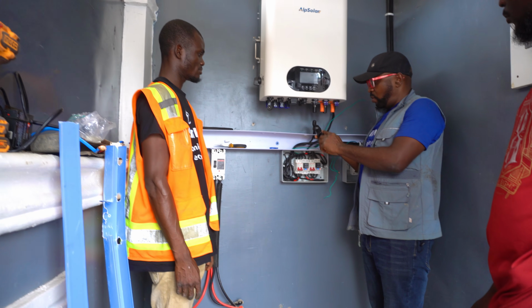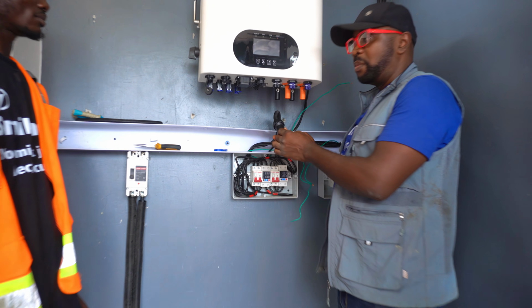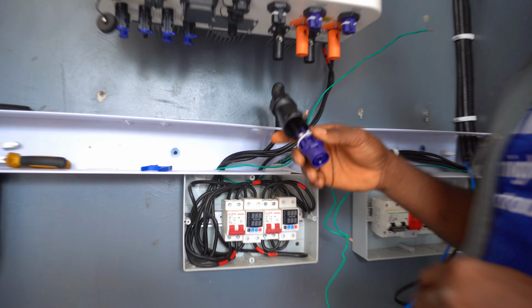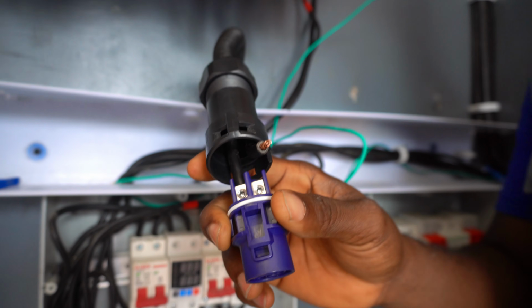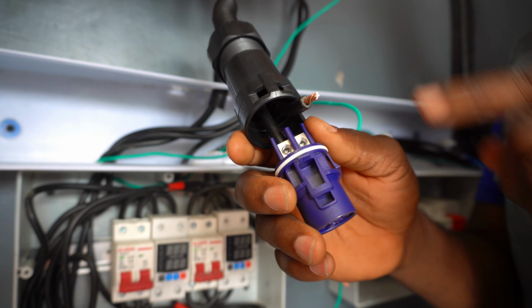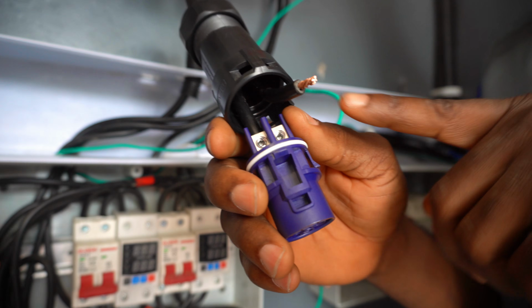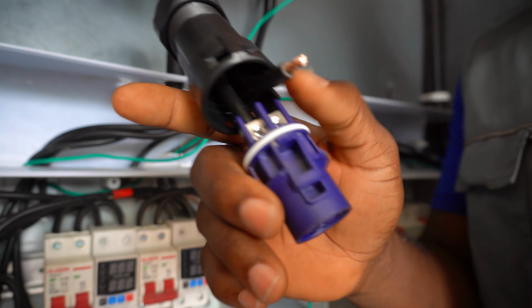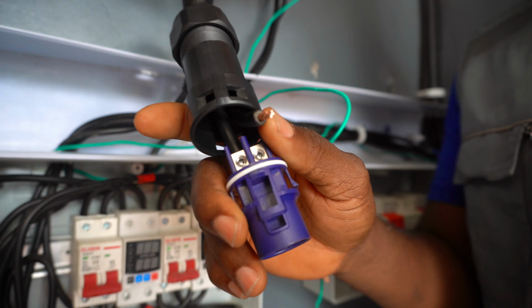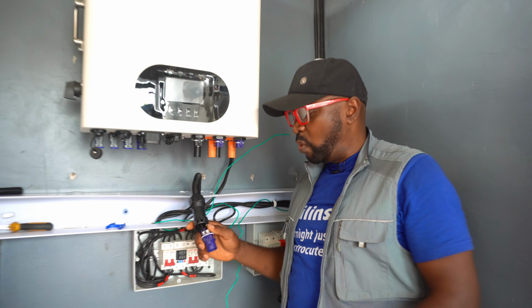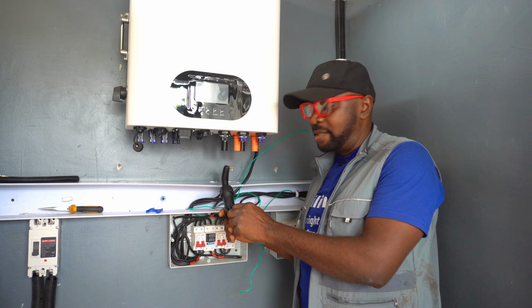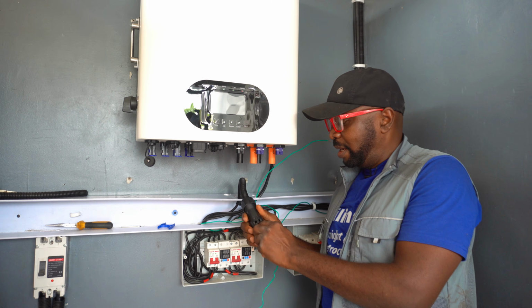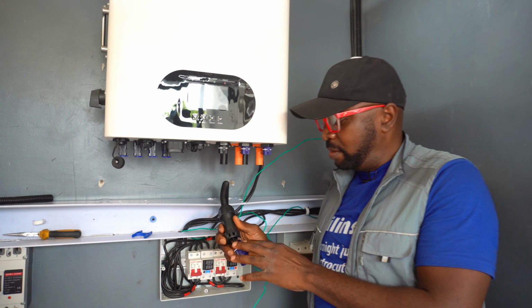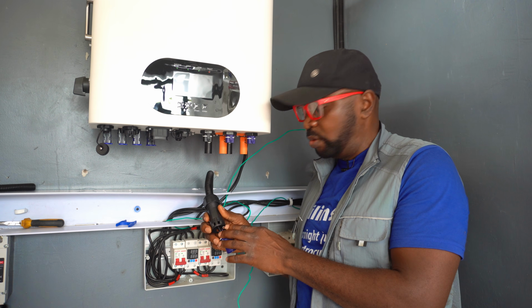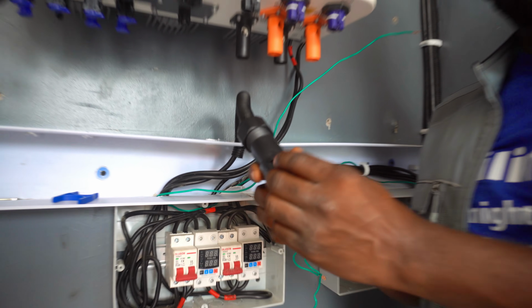So this is what we also discovered here. Most installers can actually be fooled by the marketers or producers of this cable. If you look at it, the flesh of the cable is very fat, but the copper inside is quite little. This is meant to be a 10 mm wire, but in actual fact is around 6 mm. I'm not trying to blame the installer, you can be fooled by this type of wire.